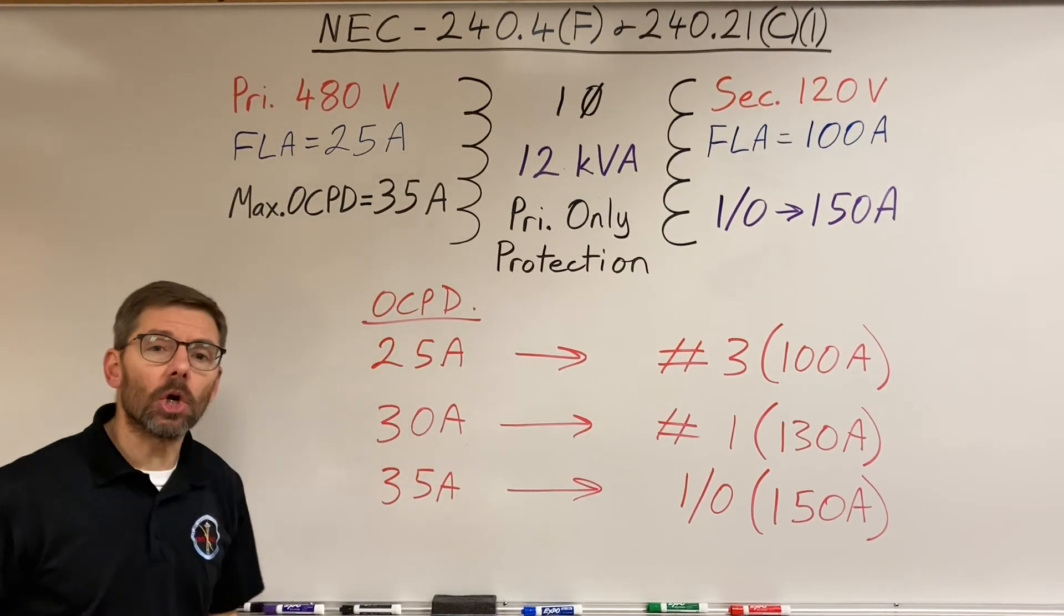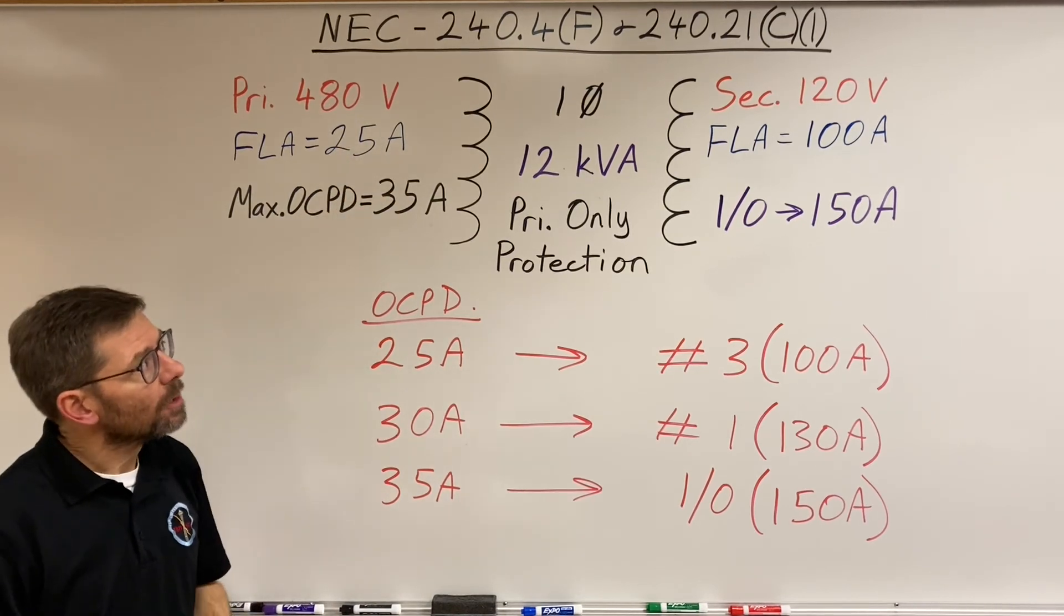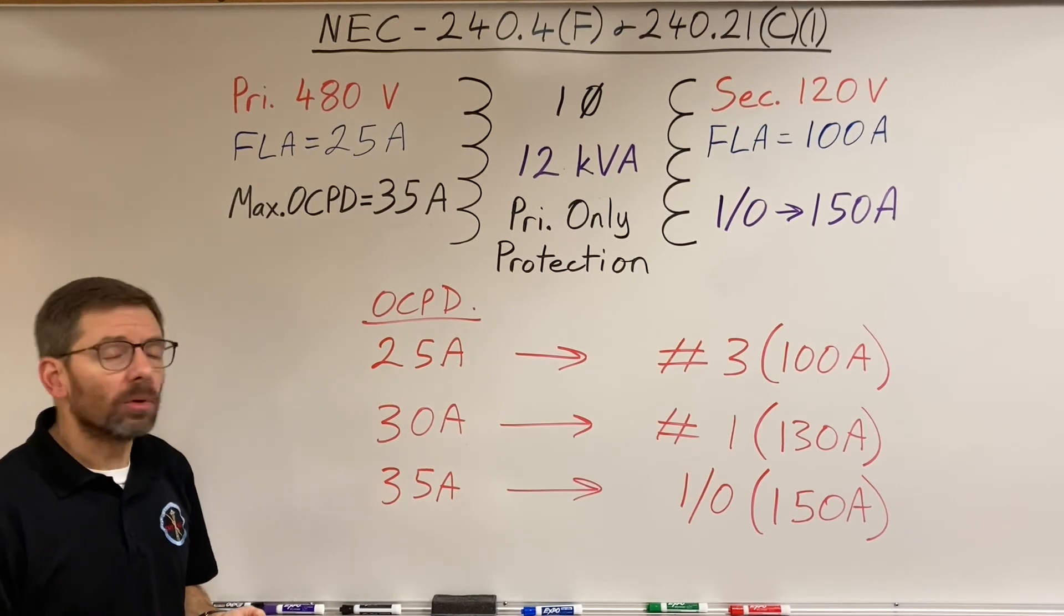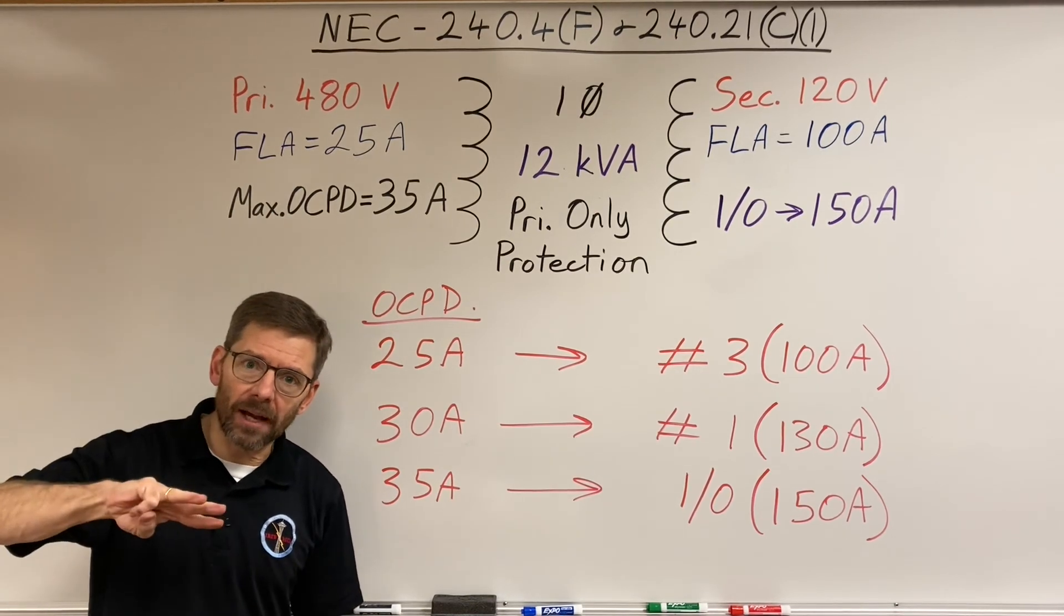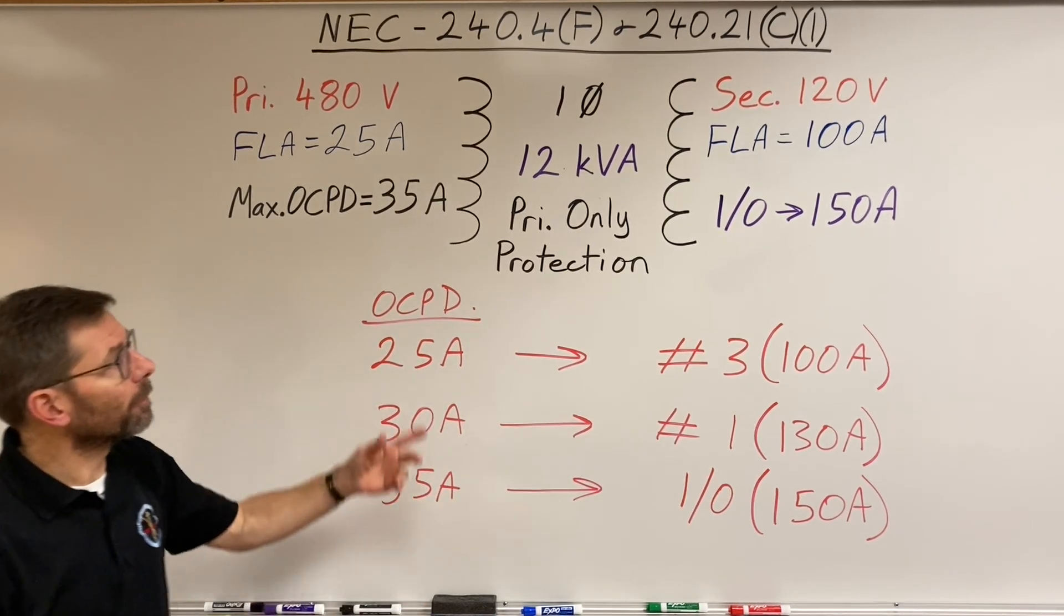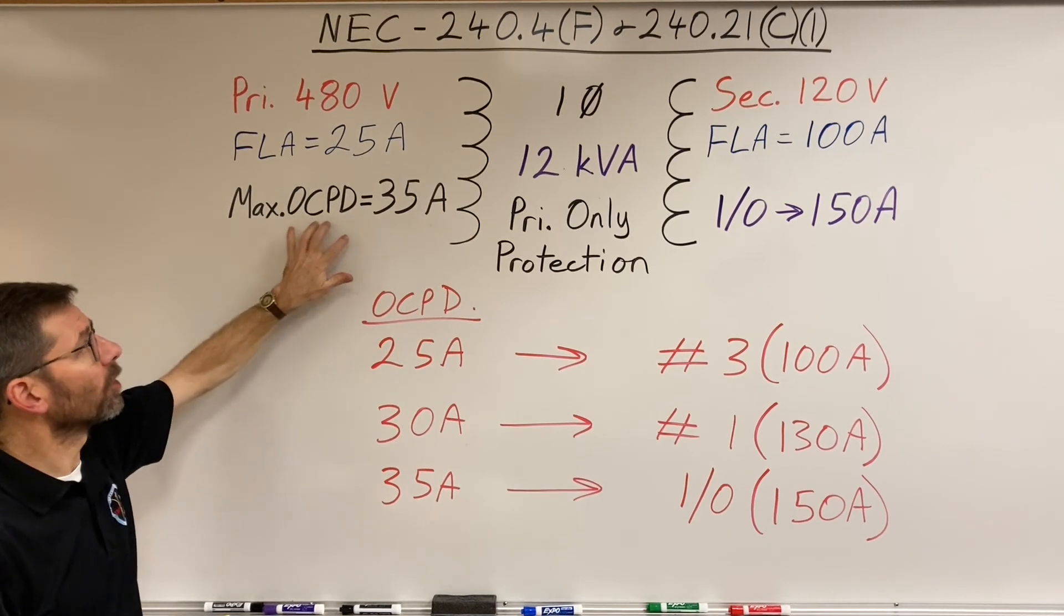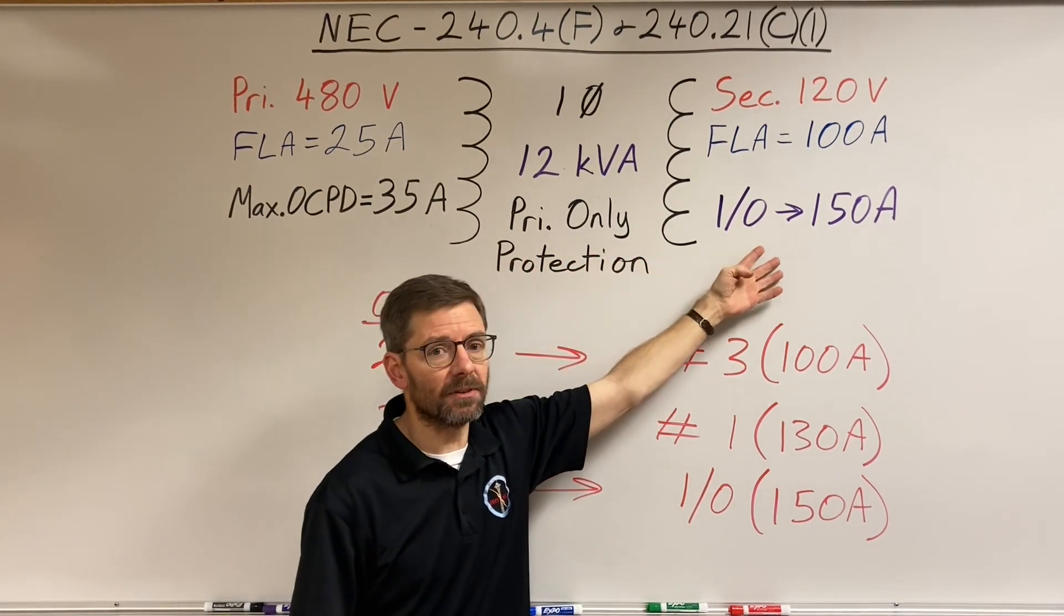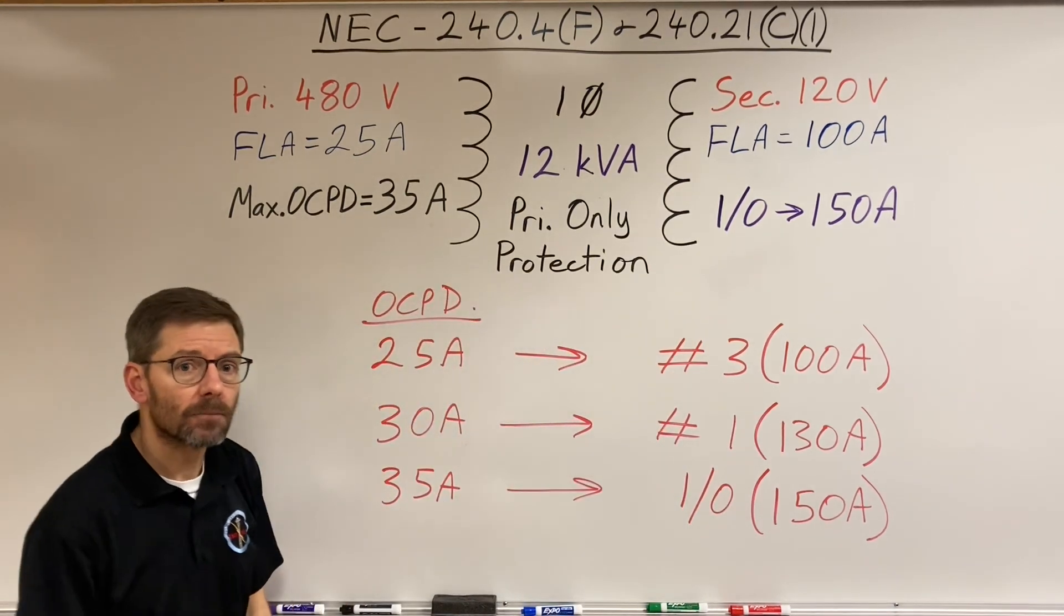So we can kind of play a negotiating game in this. That sums up what those two sections both say about transformer secondary conductors. Only those two circumstances, a two-wire single phase and a three-wire three-phase delta-delta, are when I can protect the secondary conductors with the primary overcurrent protective device. Now if we have a secondary overcurrent protective device, there's other rules in 240.21 that apply. But that's for another day.